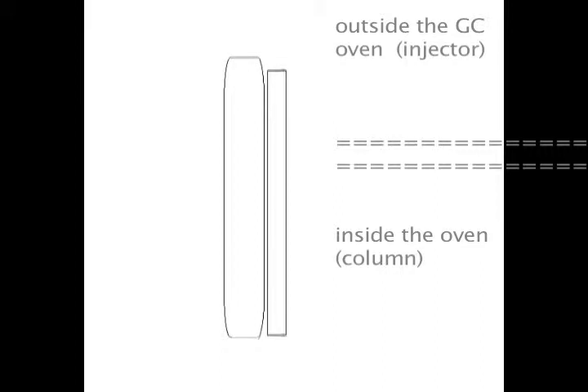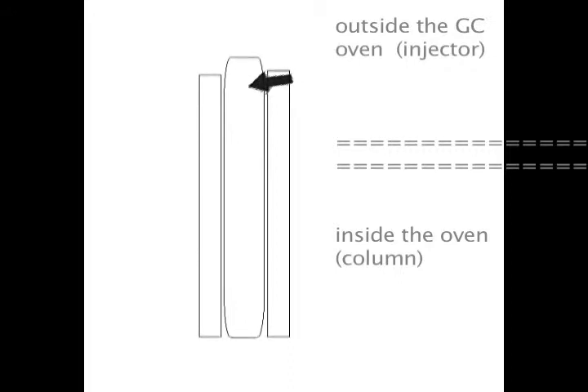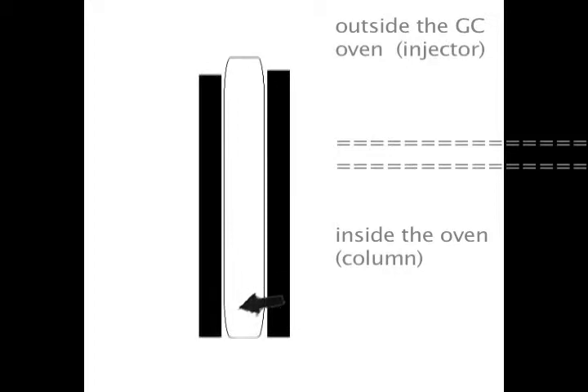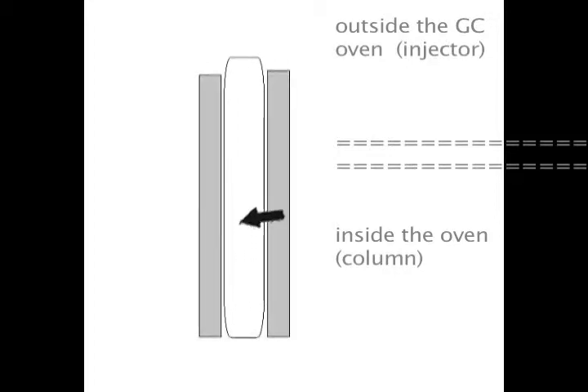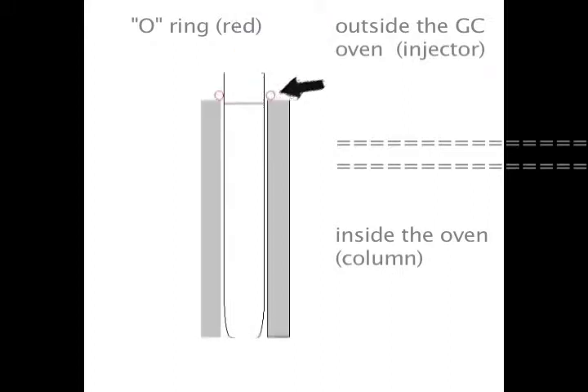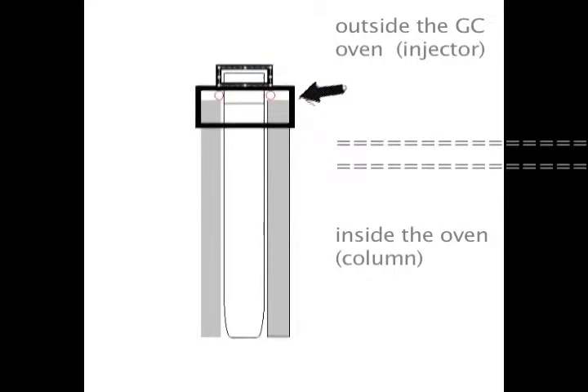Let's take a look at this. The injection system takes a lot of different forms with different gas chromatographs, but I think this is a pretty good general representation. The port liner is nothing more than a glass tube. It's about the diameter of a pencil, about two and a half inches long. It is held freely from the top and the bottom in a sleeve. The sleeve accepts a nut both on the top and on the bottom. The top has an o-ring. The o-ring is squeezed down by a nut, and so the o-ring forms the seal between the sleeve and the port liner. And then this nut also has a little place that accepts the septum, and then another nut that goes on top and holds the septum in place.